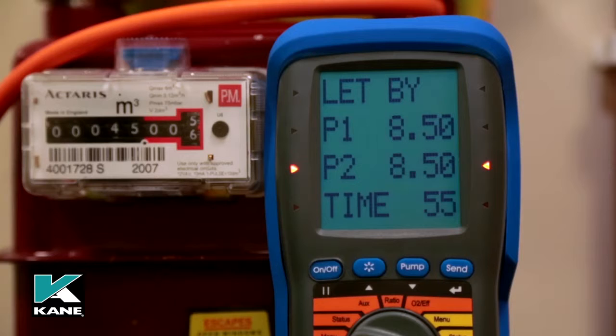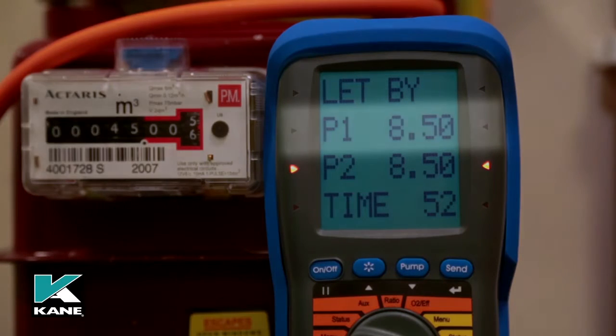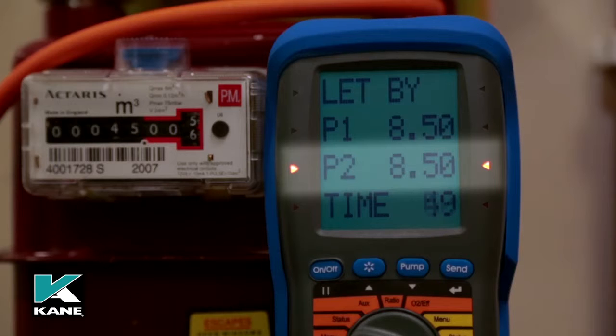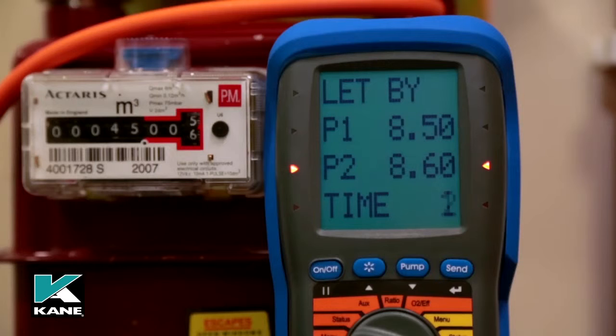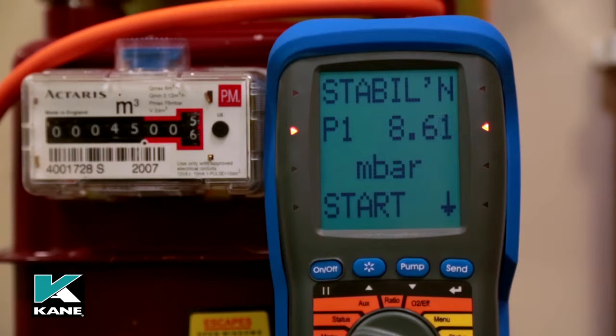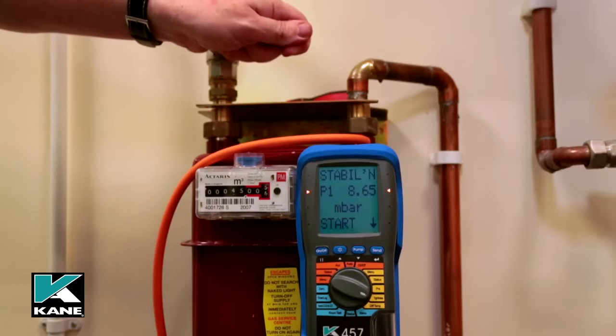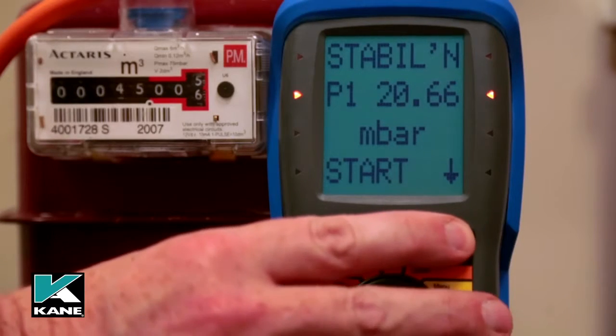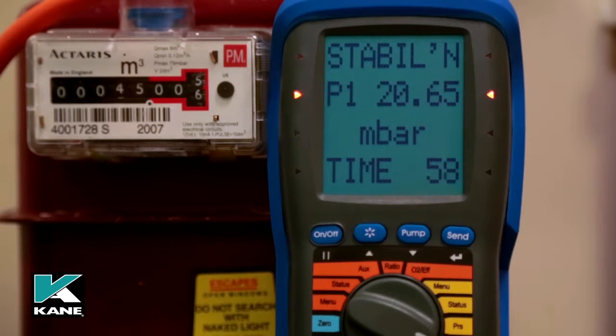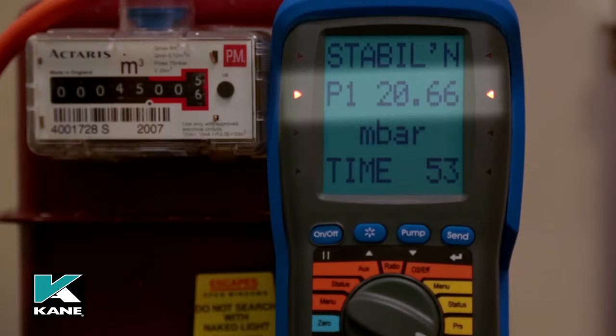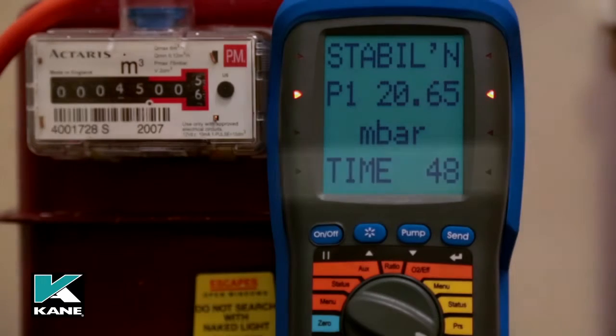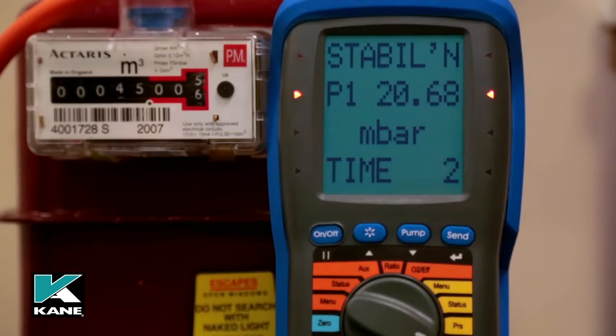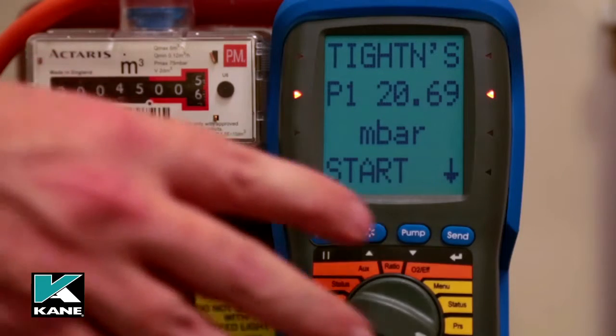The display is as follows: pressure at the start of the let-by test, real-time pressure reading, let-by default time is 1 minute, can be changed via menu. When complete, adjust the gas pressure up to 20 millibar, then press send to start the stabilization period. The display is as follows: real-time pressure reading, pressure units can be changed via menu. Stabilization default time is 1 minute, can be changed via menu. When complete, press send to start the tightness test.